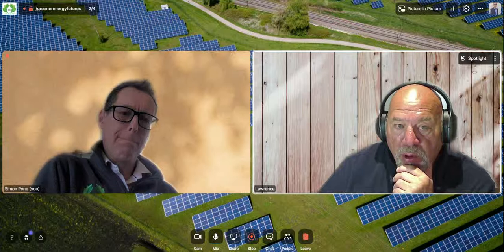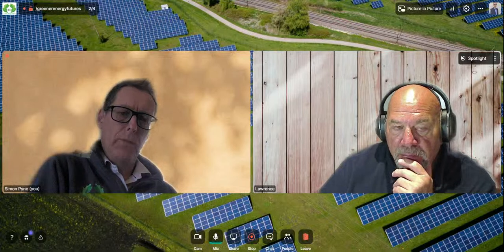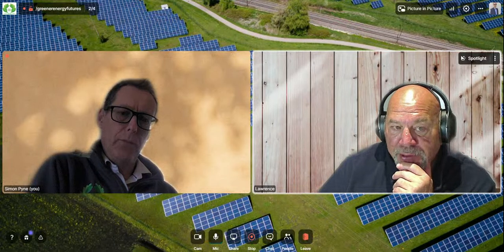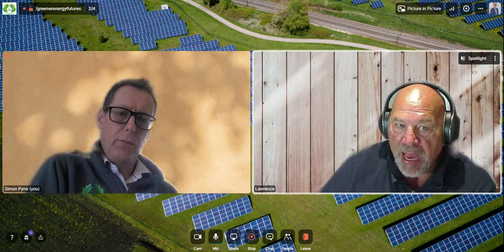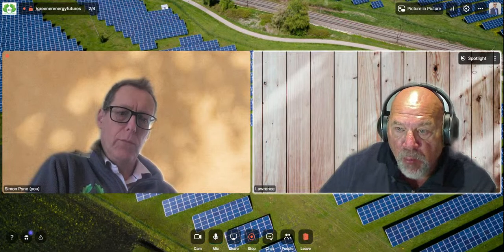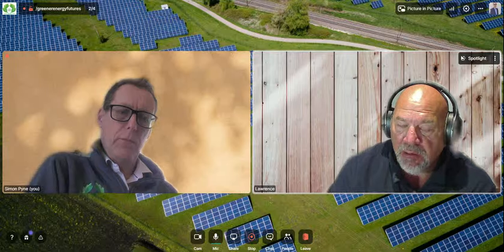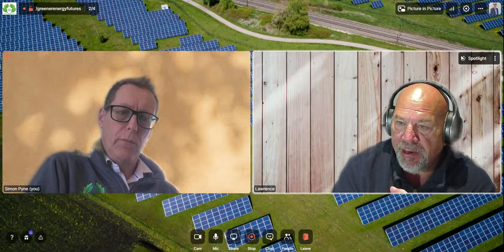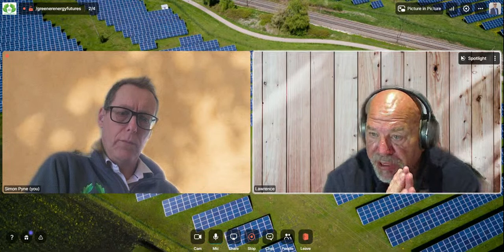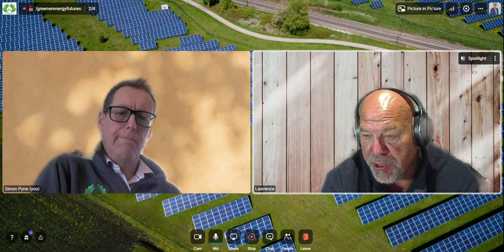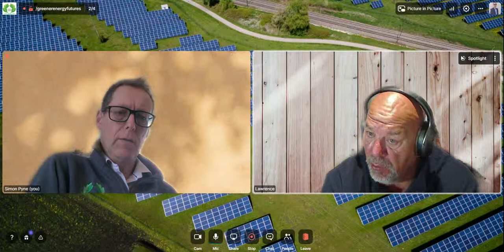If you can borrow a thermal camera, or you can do this by hand, go around, if you've got an AHU, look at all the flanges, the joints, the manway hatches. These are like inspection hatches. Make sure they're insulated. Make sure that none of these units have got missing insulation, or insulation that's been taken off so somebody can do some work and not been put back properly.